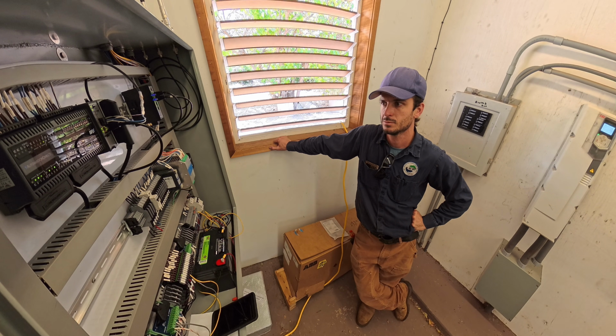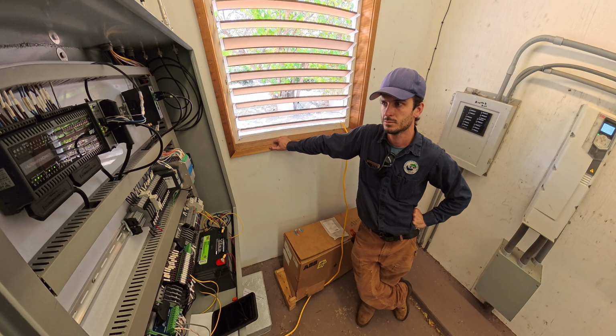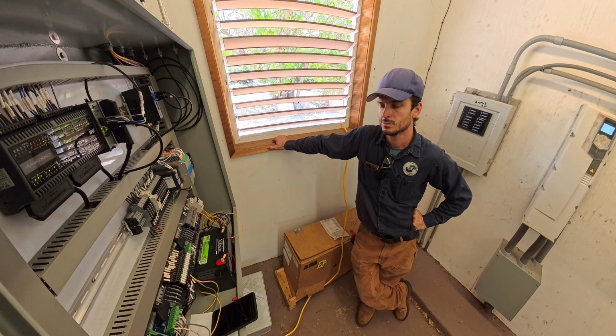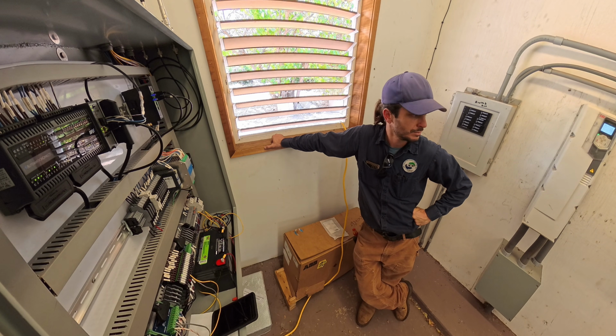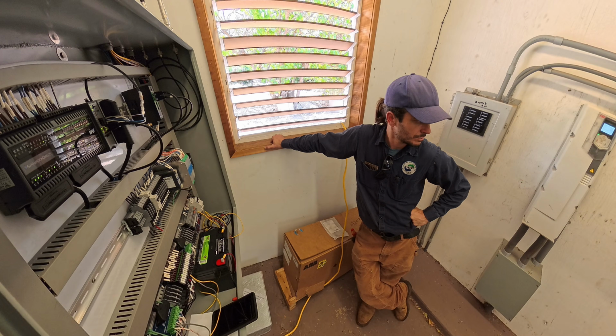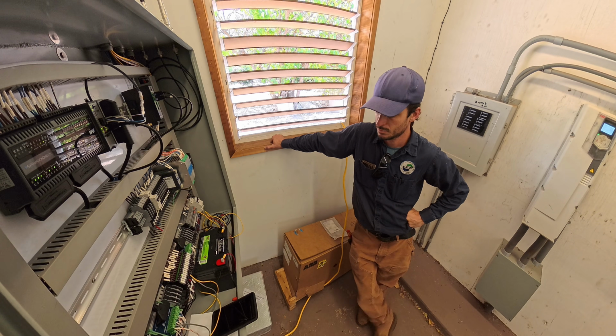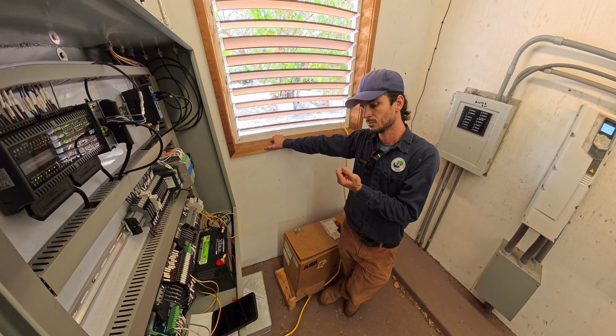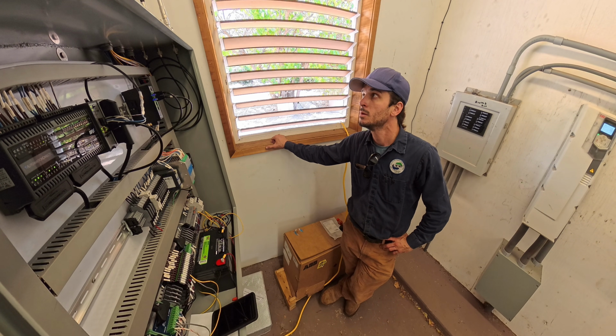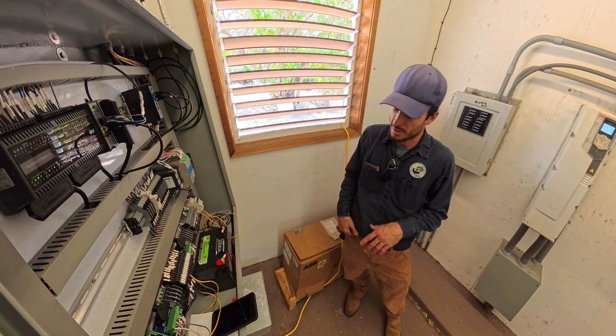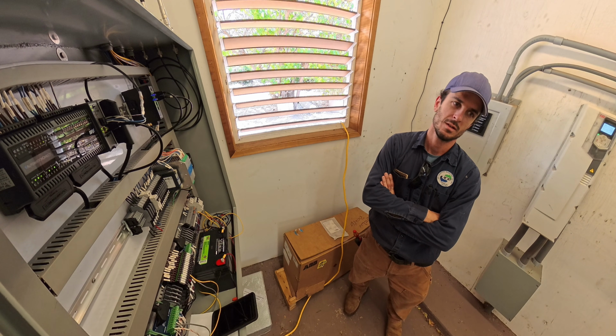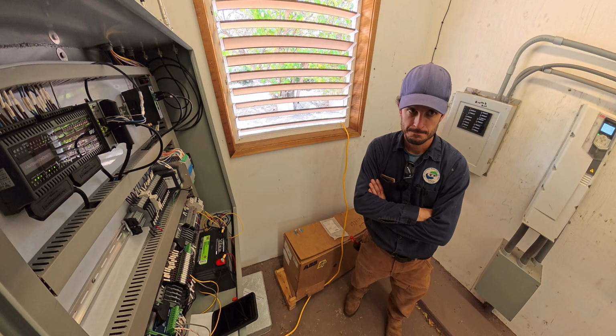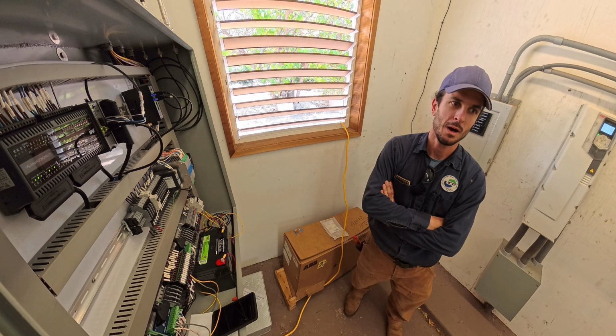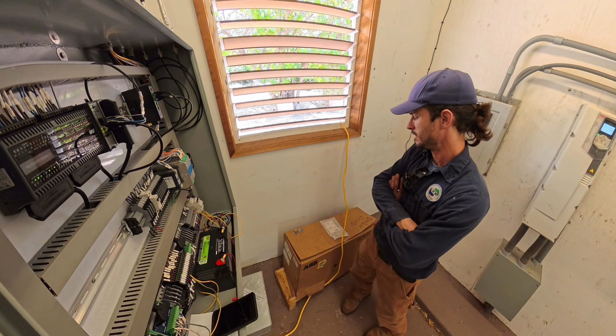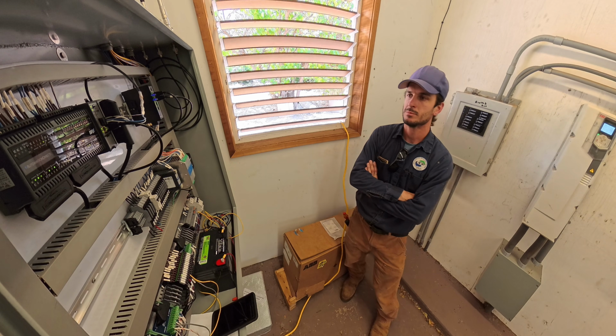Okay, and currently when there's a call for water and our cycle stop is good, and there's no failed start, and let's see, now I'm just going to add our float in, so when our float is active, we can run it. And I believe they wanted that float fault to be like a lockout that they have to reset, not automatic reset. Okay, oh good, excellent, I believe. Yeah, I mean that's how they currently have it. Right? Yeah, totally.